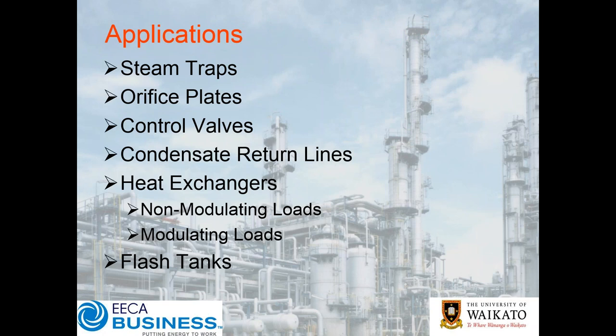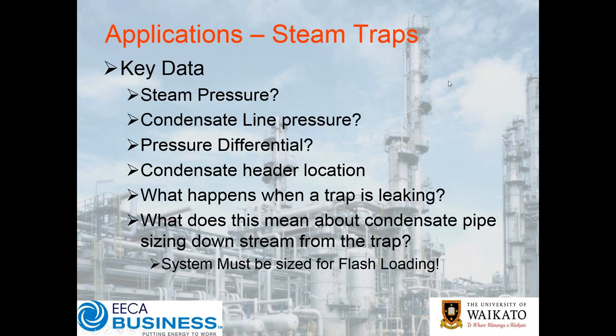Now let's look at applications: steam traps, orifice plates, control valves, condensate return lines, heat exchangers, and flash tanks. For steam traps, the key data to consider is: what is your actual steam pressure, what is the pressure of your condensate line the trap discharges into, and what back pressure that system will impose on your steam trap - because that back pressure dictates how much flash steam will be generated on the discharge side.